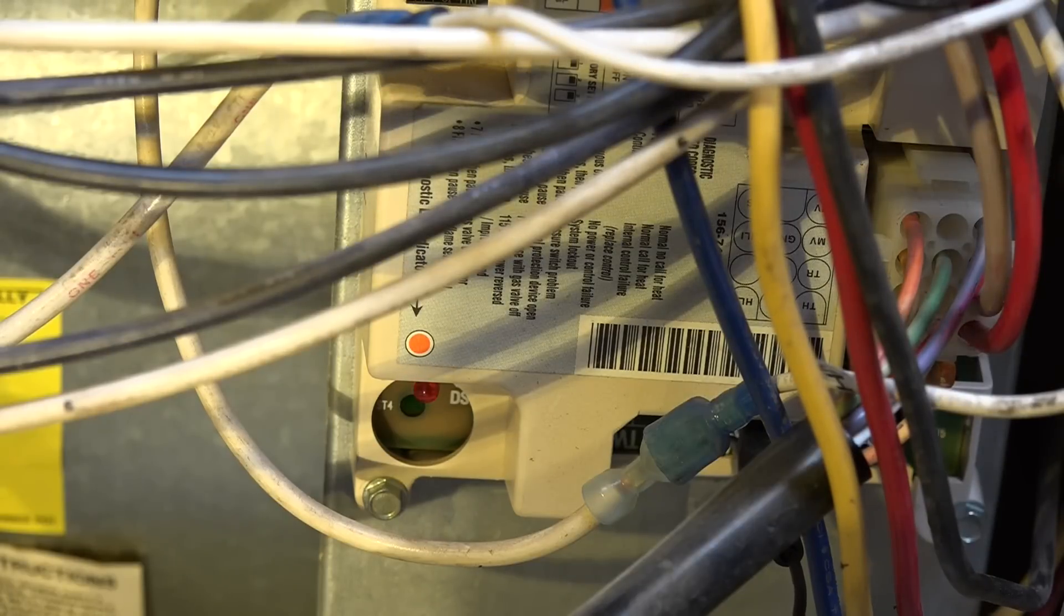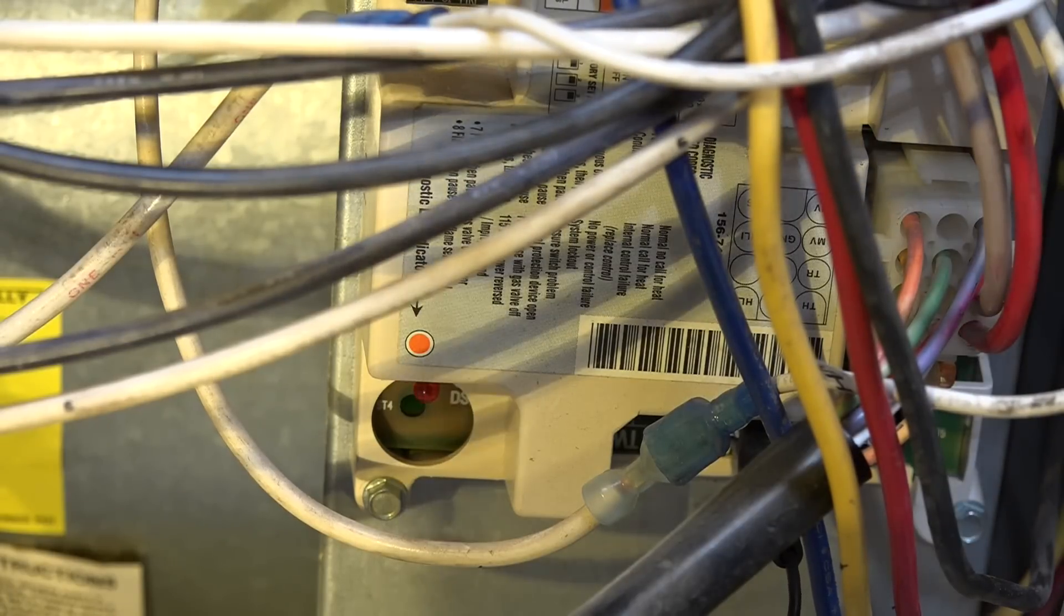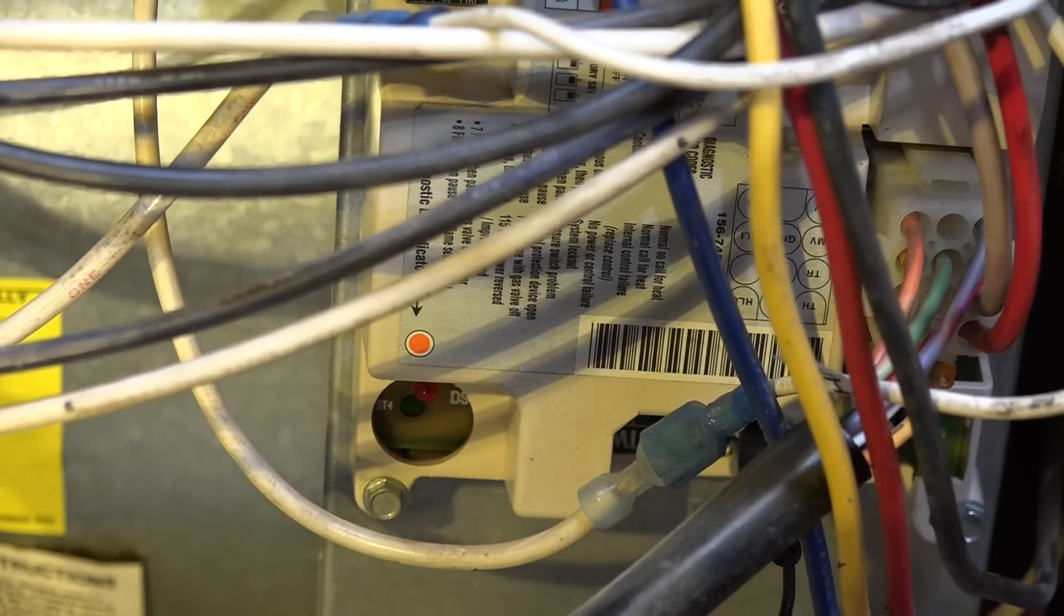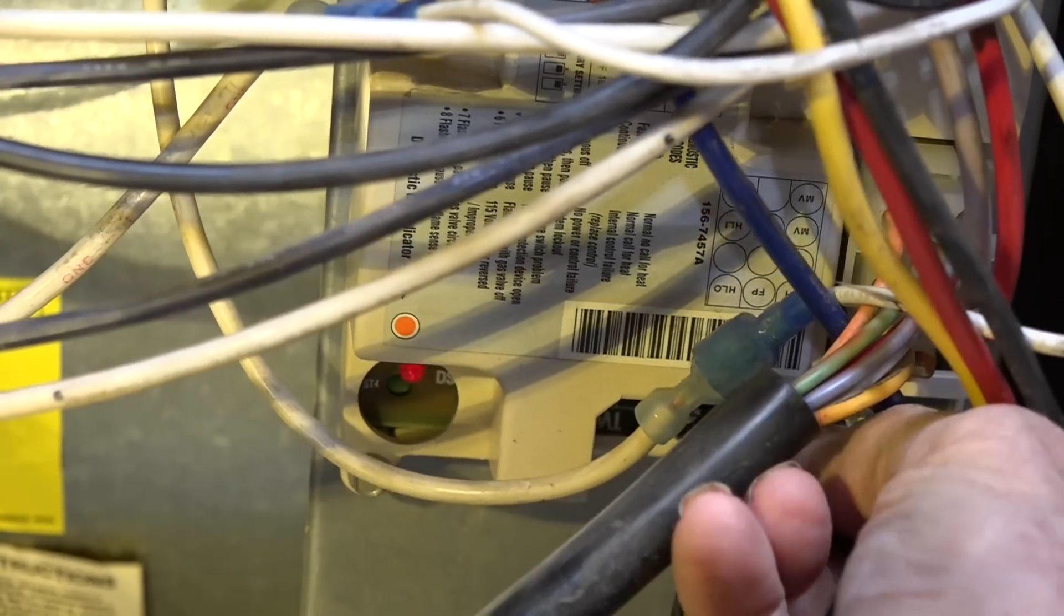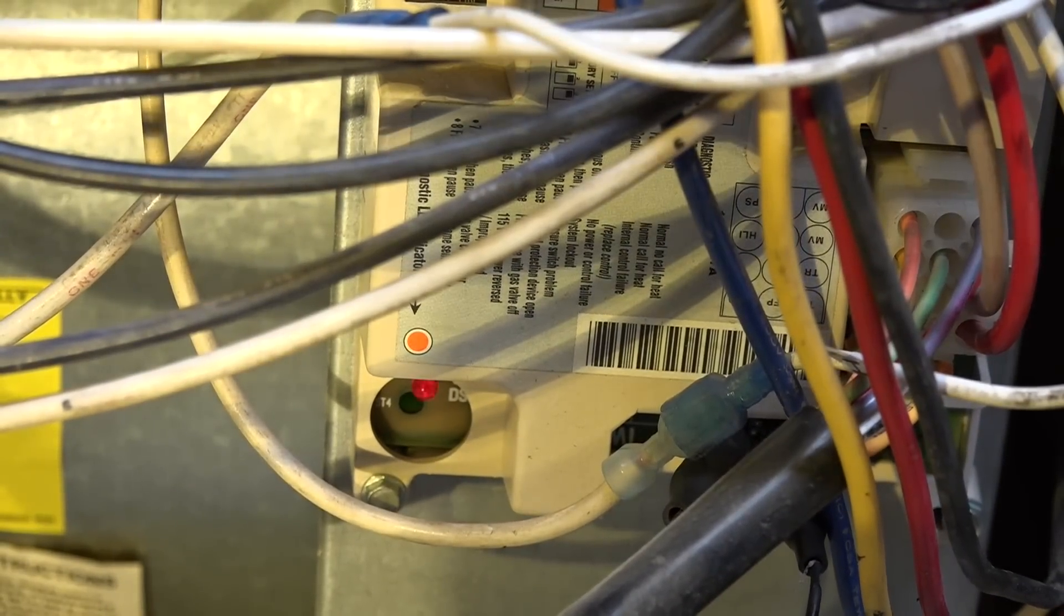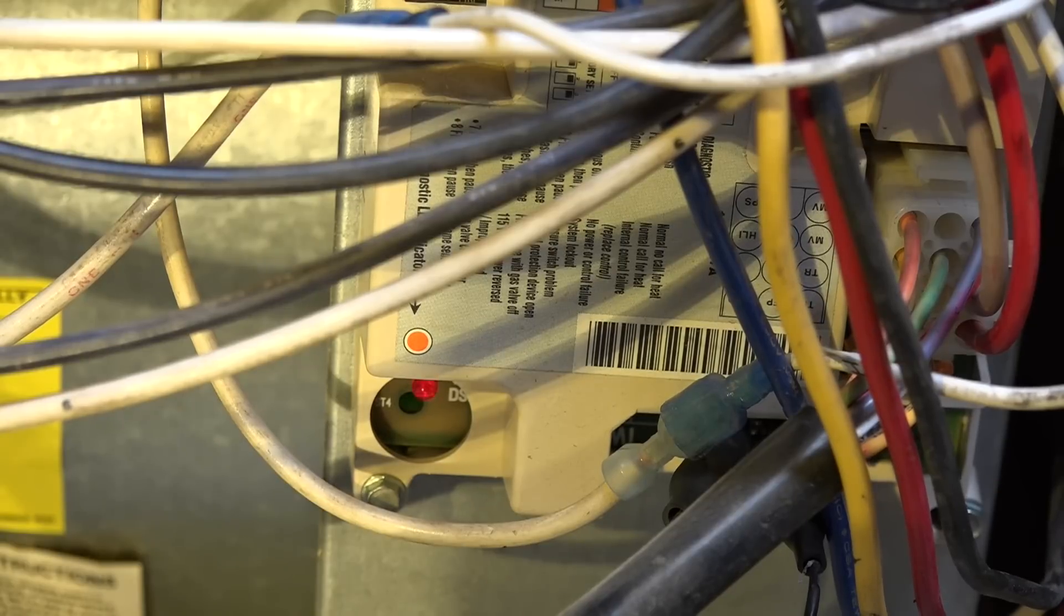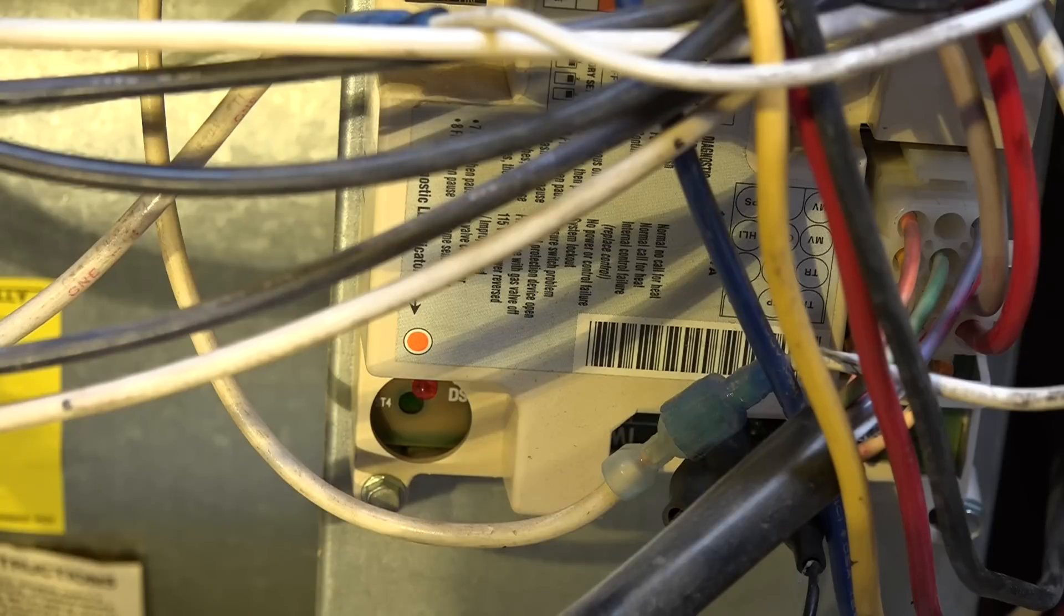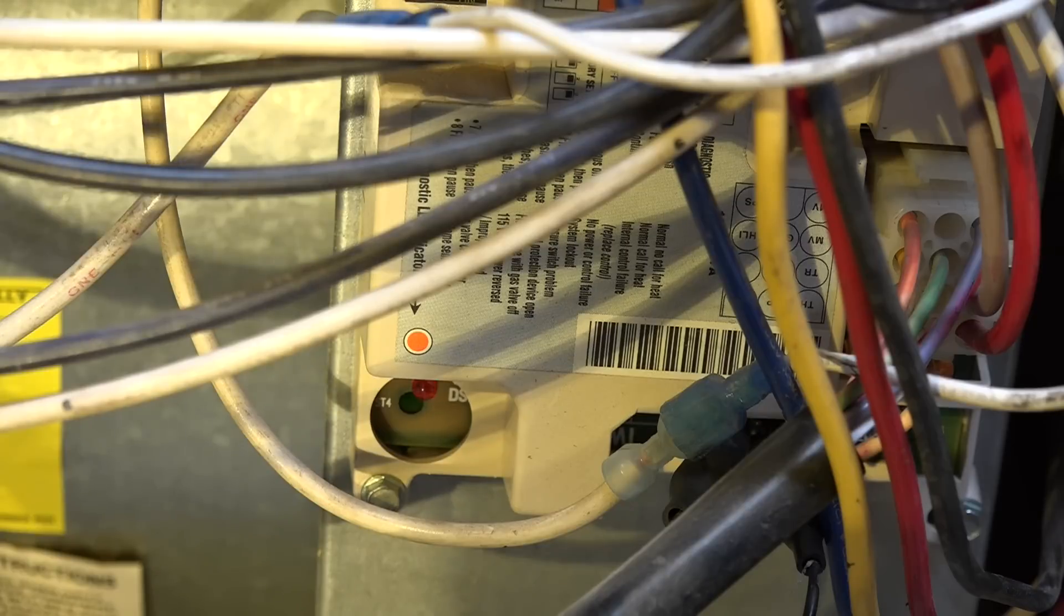Now here we're starting out with the normal slow blink and we're going to call for heat. We've got fast blink. Now you notice it only took about five or six seconds. If it didn't make that pressure switch in five or six seconds then it's going to go out on a pressure switch problem.